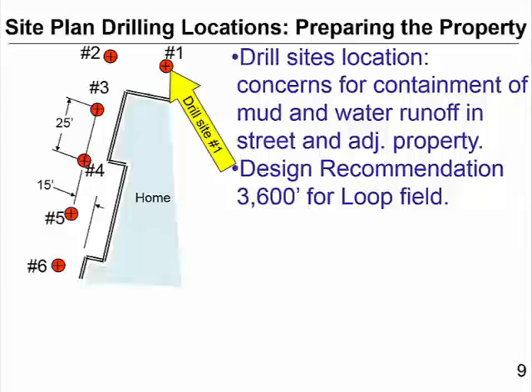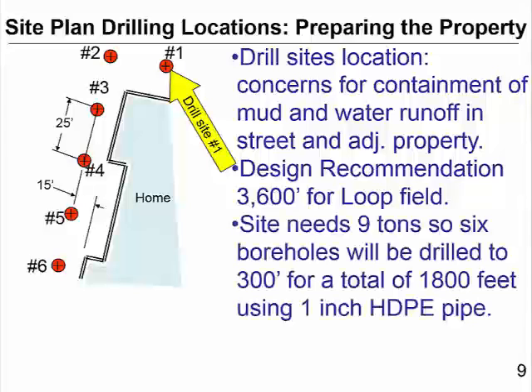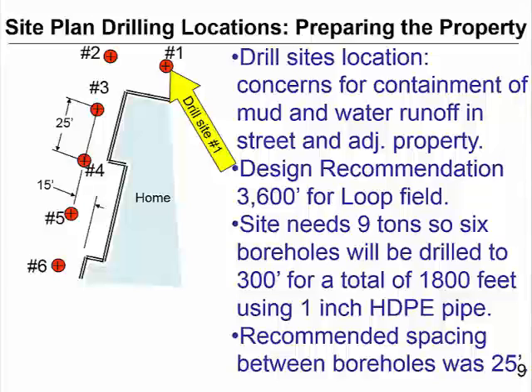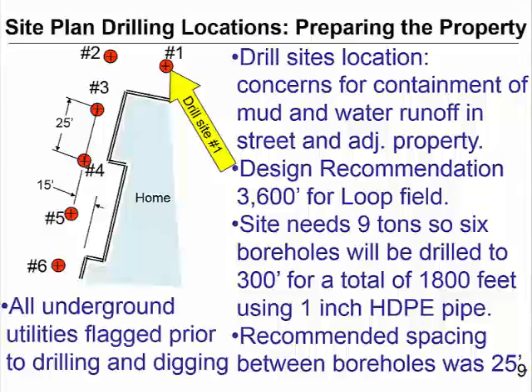So the recommendation was for 3,600 feet for the loop field. So the site needs 9 tons, so 6 boreholes will be drilled to 300 feet for a total of 1,800 feet using 1-inch HDPE pipe. The recommended spacing between the boreholes was 25 feet. All underground utilities were flagged prior to drilling and digging.